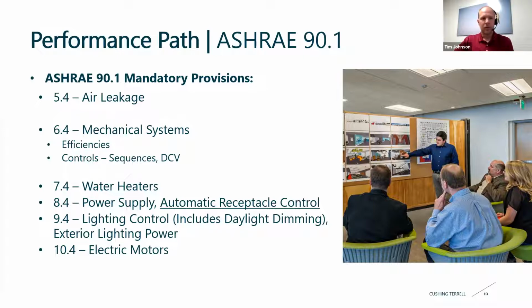Water heaters are usually not too much of an issue. The one that I find to be the biggest sticking point is Chapter 8 and the automatic receptacle controls. On certain space types, we're required to automatically control 50% of our receptacles. And that can be kind of a costly thing and kind of a nuisance to some owners, not knowing that their receptacles are going to shut off at certain times of the day or when unoccupied. So something to keep in mind if you choose the ASHRAE 90.1 path.